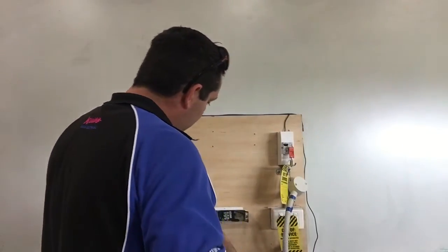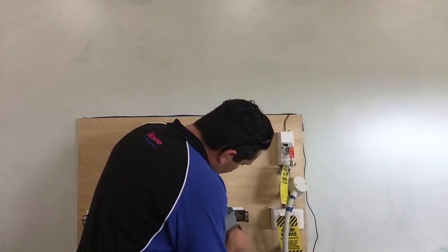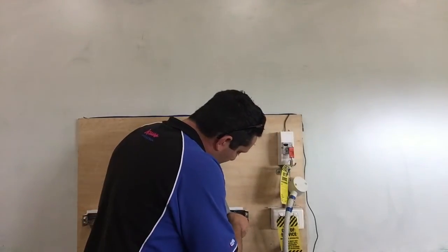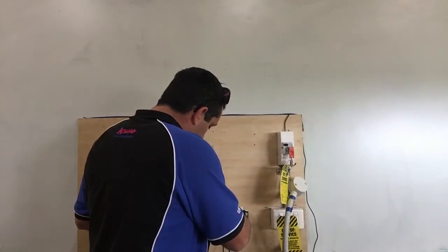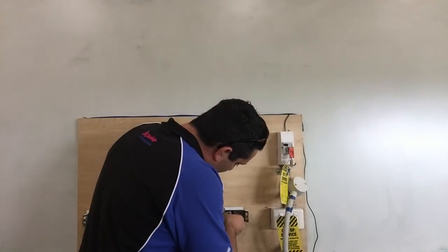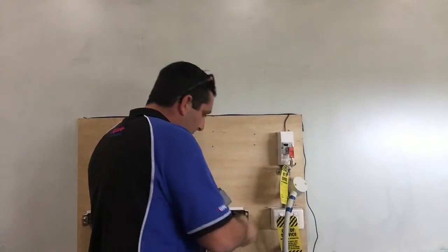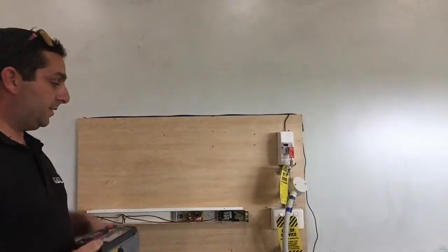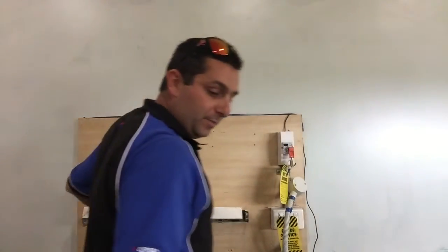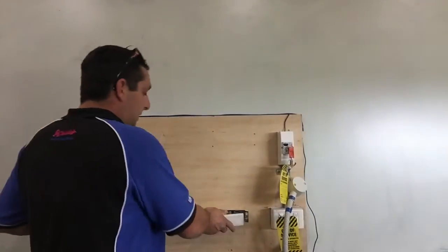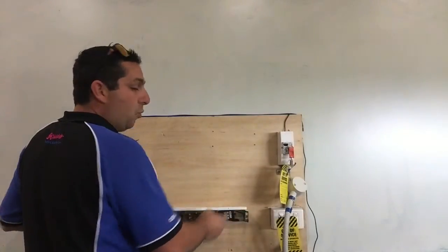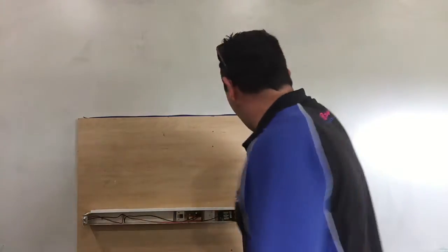We're going to test from active to earth, and we're going to test from neutral to earth. Okay, and what we're looking for is a result that is as high as possible. But in theory, it needs to be greater than 1 megohm or 1 million ohms. Unless it's an appliance that has a sheathed element, then it can be 0.01 of a megohm or 10,000 ohms.